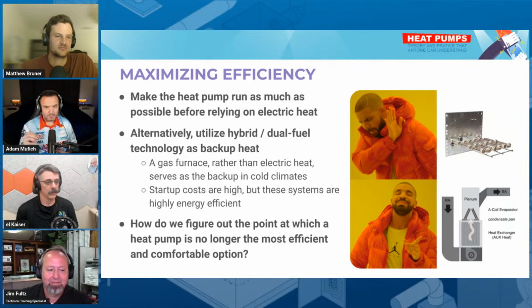And one thing I don't think we really mentioned is that thermal balance point is something that you actually get by running a Manual J load calculation and then following the Manual S process. That's a point that is actually given to you based on the performance data of the equipment that you enter in Manual S. Mm-hmm.